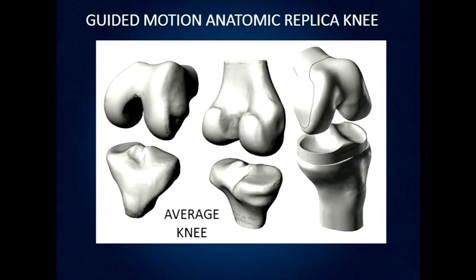Why don't we go one step further and make sure the components fit nicely in the knee with anatomical surfaces? The reason is you want the ligaments, soft tissues, and muscles to flow over the implant at all angles of flexion as they would in the normal anatomical knee. We use the average knee data from those multicolored MRI overlays — we could design a patient-specific knee, but at the moment we're into averages. Here's the average knee and here's the average total knee replacement, with guided motion bearing surfaces on the end, assuming we remove the cruciates as surgeons prefer for moderate to severe cases.